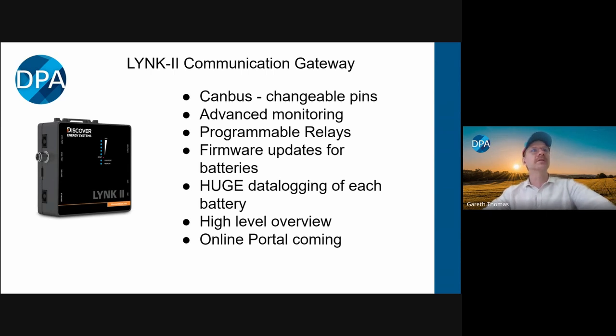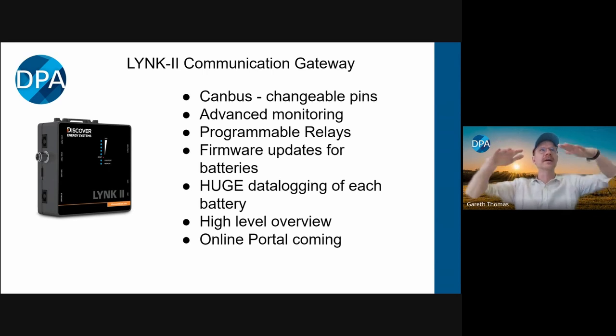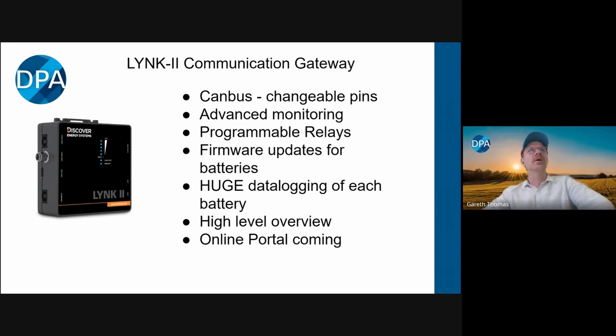It makes an enormous difference if you have a large amount of batteries. Say you're doing a big install in the middle of nowhere and you want to make sure it's all working properly - when you plug it in and commission it, you can see all the batteries leveling out with each other, and you can see if any of them aren't pulling their weight or aren't switched on. Whereas with other systems, it's much harder to detect those issues until the battery actually fails or has a warning light. So you have that overview, and there's an online portal being launched any day now where you'll be able to see all of this online as well. But I'll come to this in more detail in a moment.